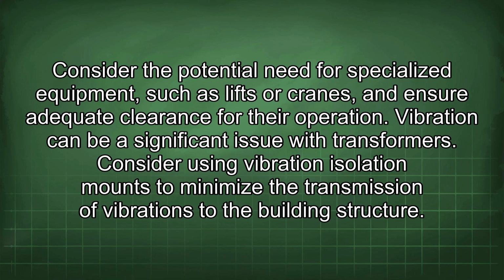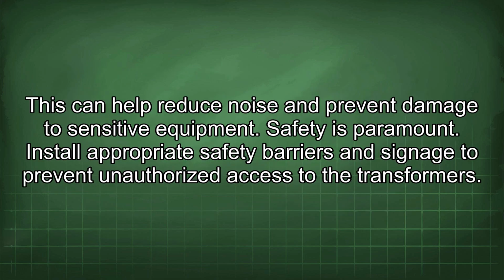Vibration can be a significant issue with transformers. Consider using vibration isolation mounts to minimize the transmission of vibrations to the building structure. This can help reduce noise and prevent damage to sensitive equipment.